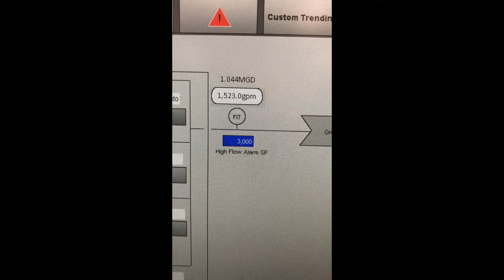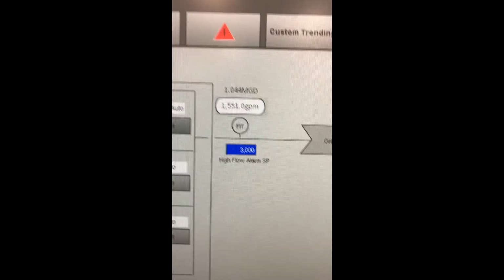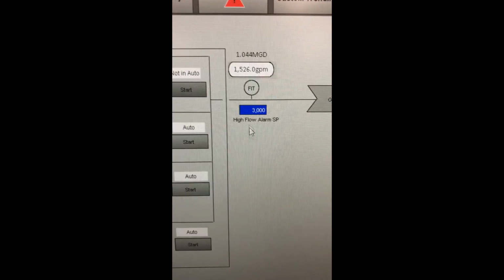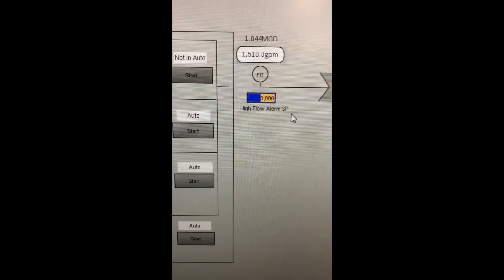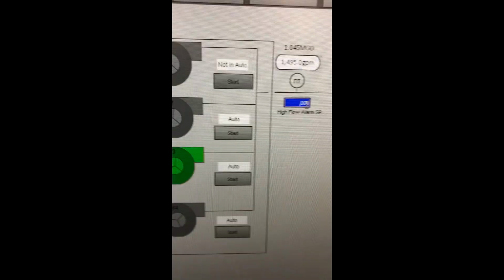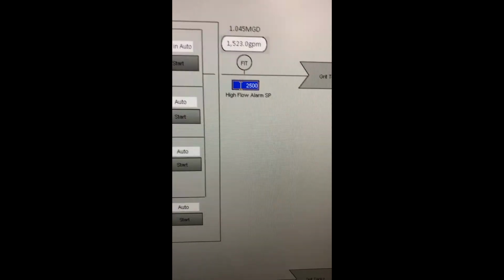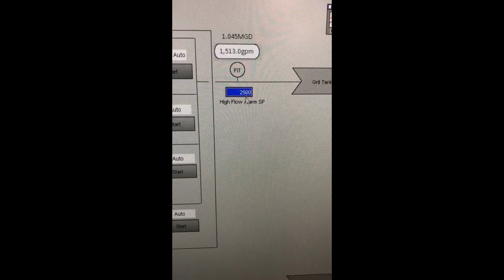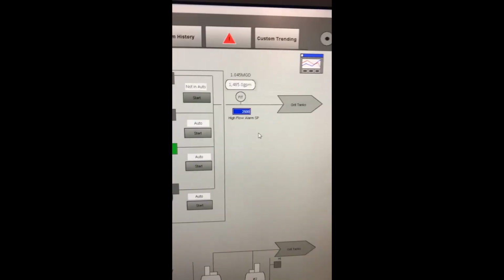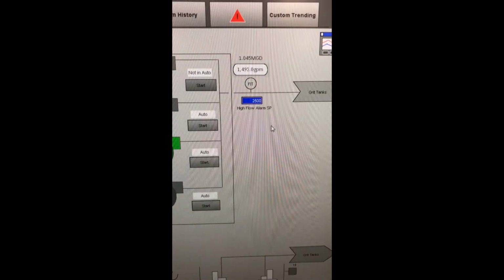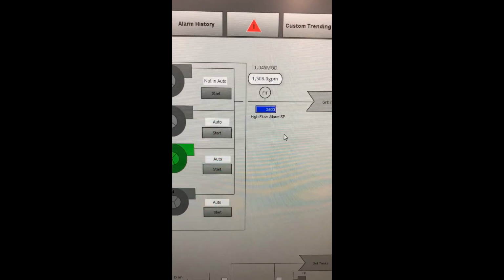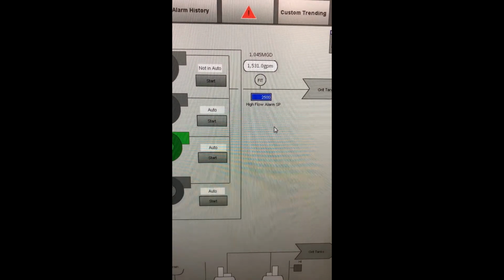I just want to show you something I put in here recently. The operators can adjust this set point here, but if for some reason we ever see a flow that's right now above 3,000, and we can make it 2,500 or 3,000, whatever they want. If the flow goes higher than that set point, then we'll get an alarm, and we use that for, well, the biggest thing is we have another agency that sometimes, without letting us know, will send us a lot of flow, and that's not a good thing if we're not really prepared for it.